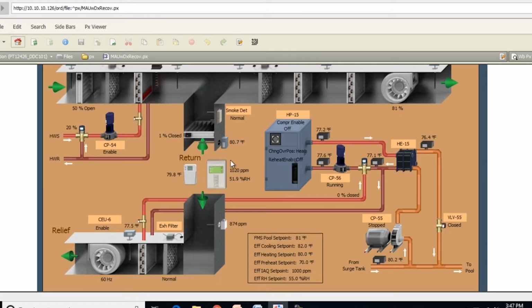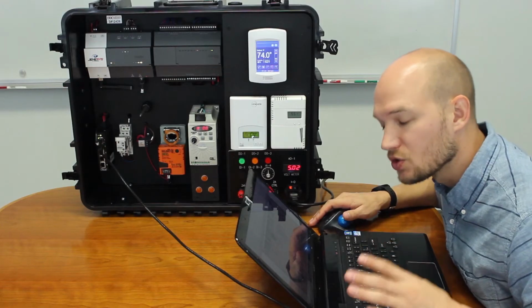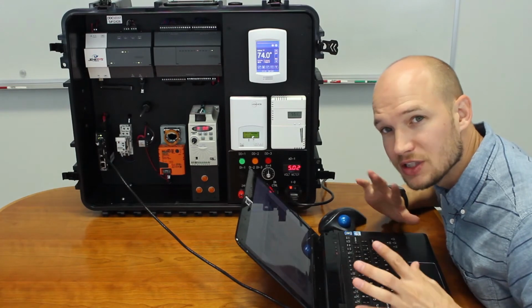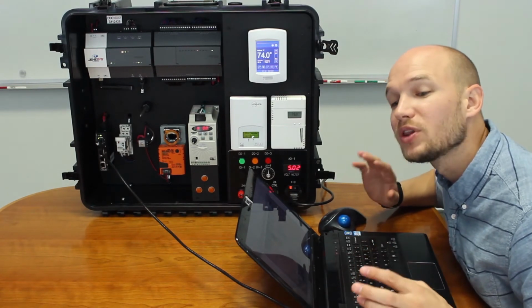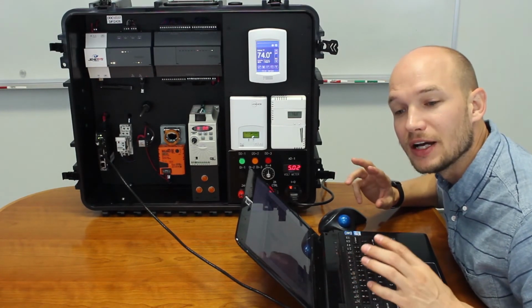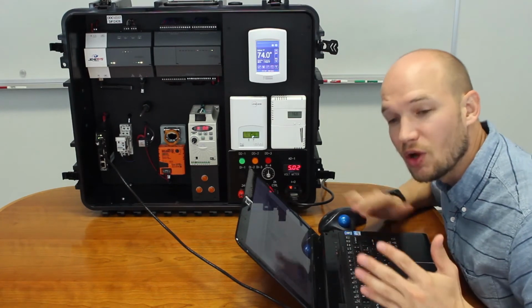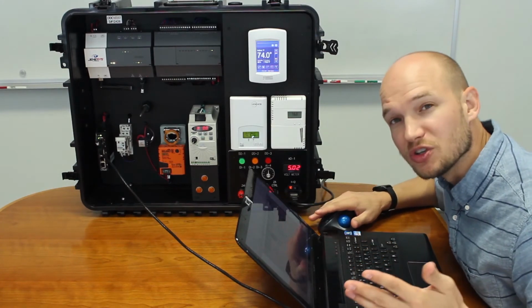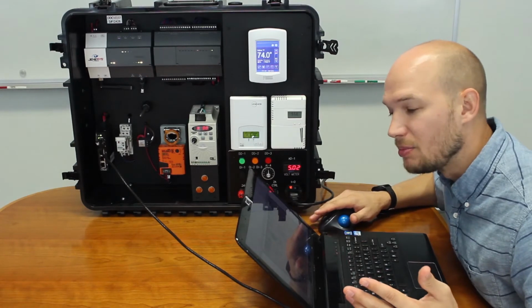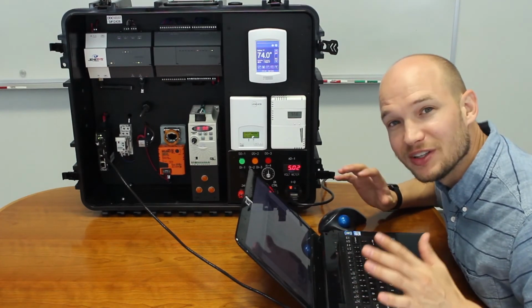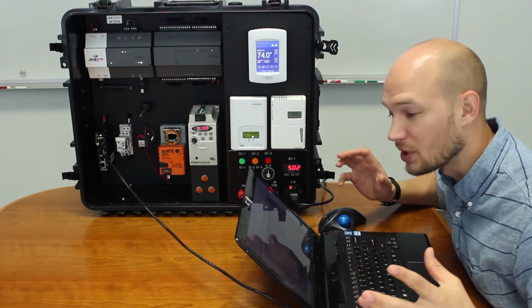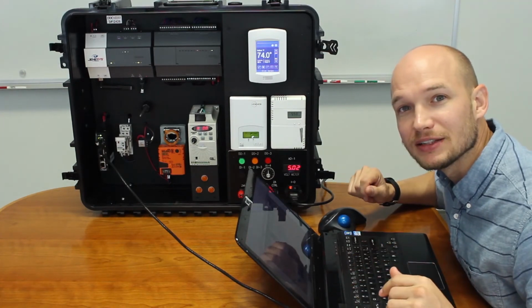You know, if this parts per million gets too high, what are we going to do? And so that's what the controller is doing. It's taking all of these inputs and outputs, and based on what the programmer or the integrator designed it to be, it's going to do all this stuff automatically, unless the user goes in and overrides it, of course. But digital and analog inputs and outputs are very important. They're the backbone of a BAS system.